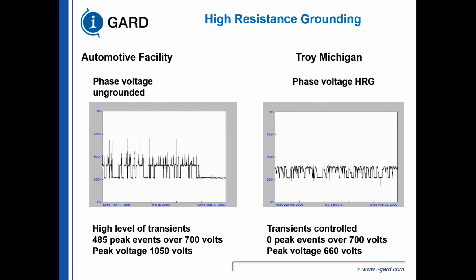we converted that system from an ungrounded system to a resistance grounded system, and we went from 485 peak voltages over 700 volts, and the peak voltage at 1050 volts, to 0 peak voltage events over 700 volts, and obviously the peak voltage was 660 volts. So it improved this facility tremendously, specifically because the peak voltages were reduced, and we didn't have any of those transient overvoltages we had in the ungrounded system when we converted to the resistance grounded system.